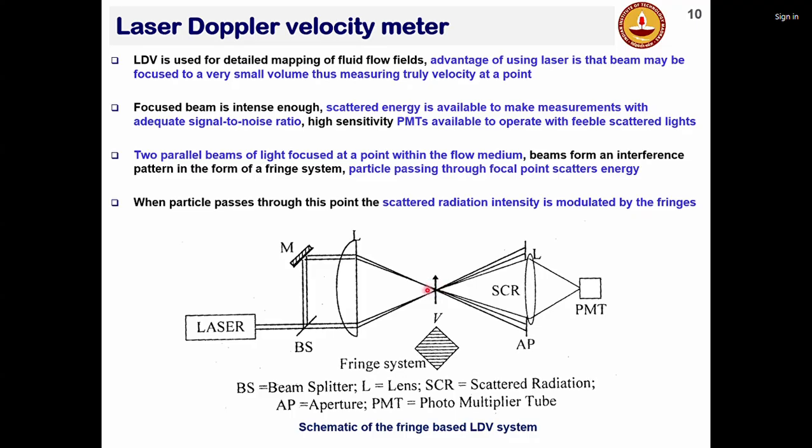And you actually use an optical detector system. For example, one kind of optical detector system is called a PMT, or photomultiplier tube. The purpose of the PMT is to collect the light signal and convert it into electrical energy. That is the purpose of photomultiplier tubes, or PMTs.